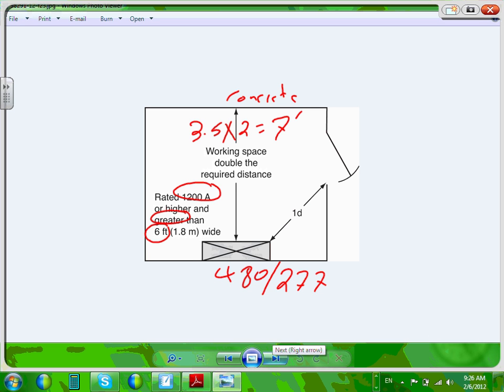Except, do you guys see the edge here? This is also another requirement to apply this rule. The distance from here to the door, when your friend Chad is working on the equipment right here, and his eyes are on it, and there's big fire coming out of it, and he wants to get the heck out of there, right? He's getting fat and fluffy, he can't run fast, so you need that distance to be 1D. What's 1D? This cannot be more than 1D, which is 3.5. The D is based on the clearances and the condition. So the switchgear cannot be placed further than 3.5 feet from the edge of the door. Does that make sense? Why? To allow Mr. Electrician to get the heck out of there upon the big explosion in the switchgear. That's the whole idea, safety.